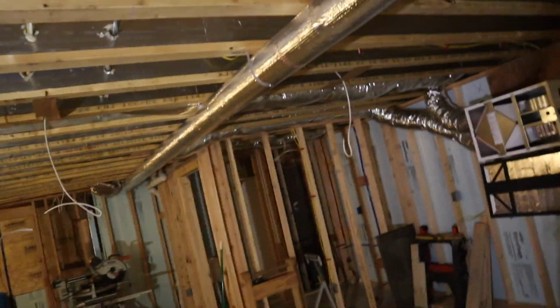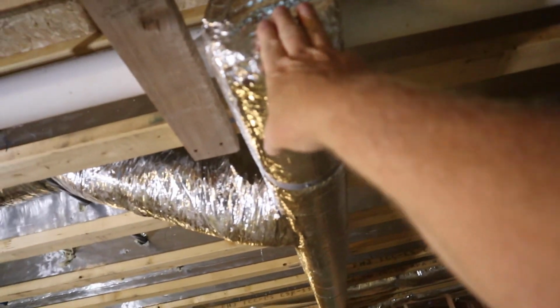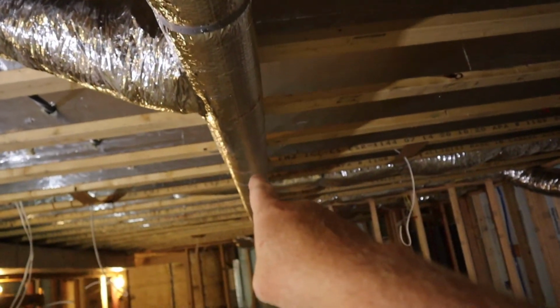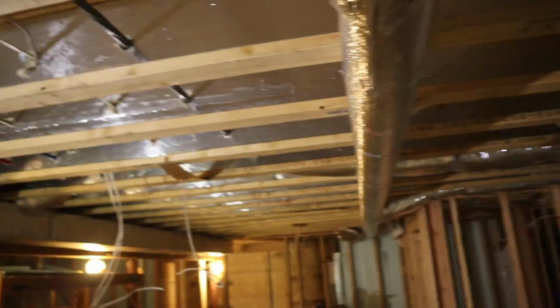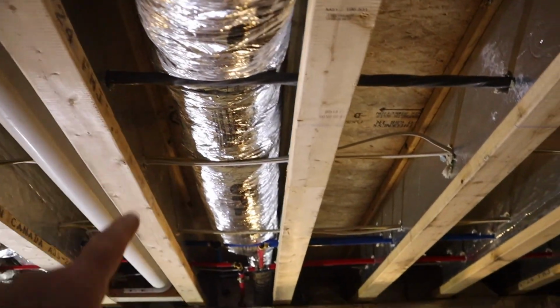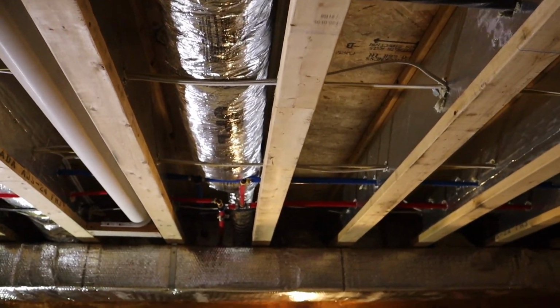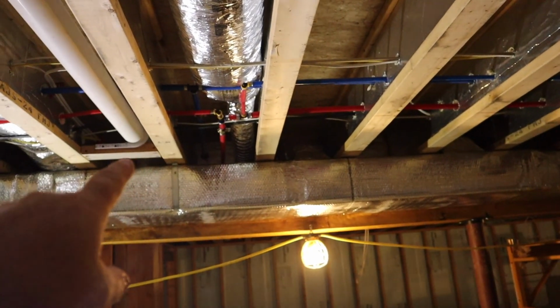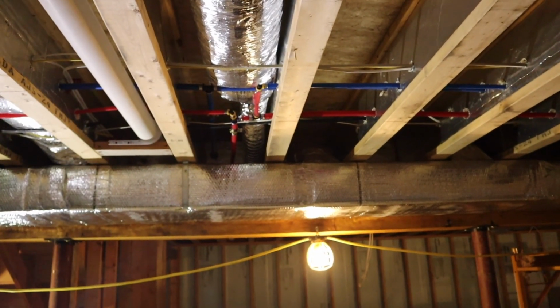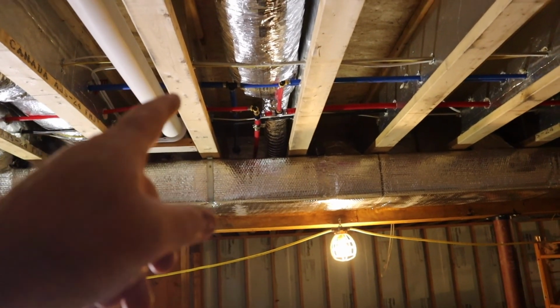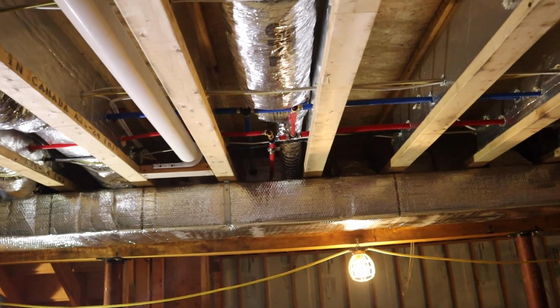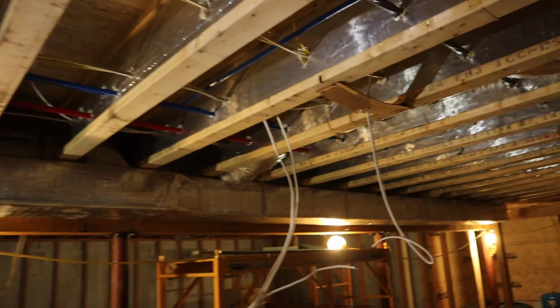All right, so we put a 6-inch trunk right here, all the way down in the basement. This one picks up the master bath. You can see the 4-inch there, it's 4-inch up in the wall so we could get it in a 2x4 wall. And then it comes to an increaser to the 6-inch flex duct to this.